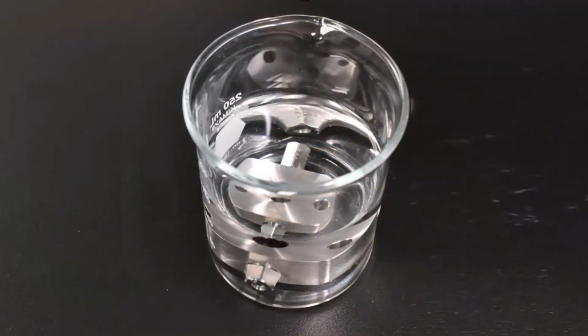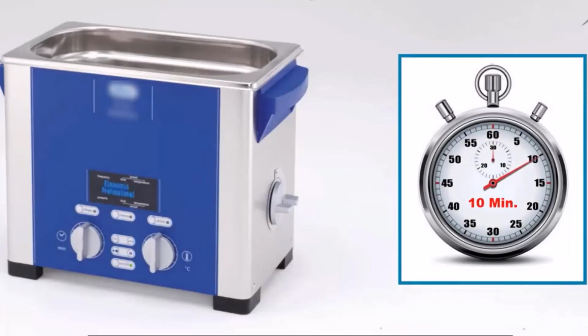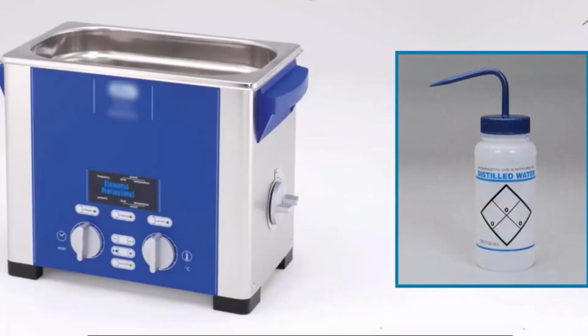Put the pump head and the check valves in a beaker containing 50% isopropanol and water. Do not remove the check valves. Sonicate for 10 minutes and then rinse with distilled water.